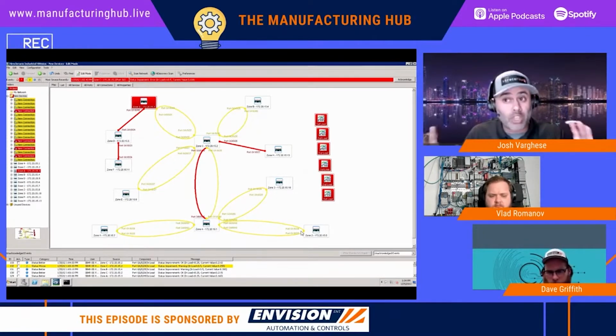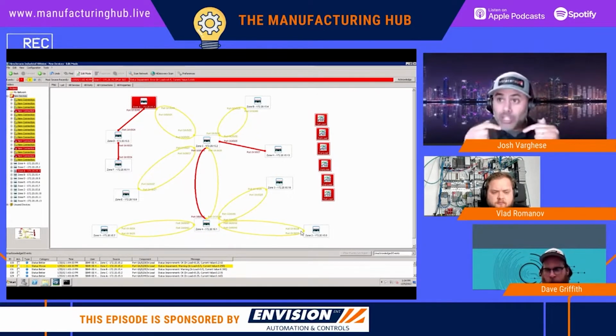But for a significant period of time, produce, consume messaging was by default inherently multicast messaging, meaning if you set up a producer of a tag, great. Even if you only set up one consumer of that tag from the programming standpoint in the PLC program, the issue is the producer is putting that on the wire as a multicast message. And here's the thing about multicast messages: that destination of 239, it literally maps explicitly to a specific MAC address.